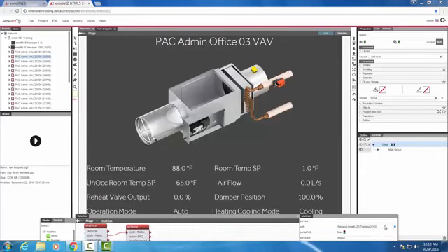In this how-to, I'm going to show you how to create a template graphic using the Relativize block. So this is what I'm going to show you how to do. If I've created this VAV template and I want to switch out the device reference so that my graphic is a template, I would just change the value of the Relativize block. Notice on the bottom here how I am changing the device reference from 20102 to 20103, etc. And you can see all of the values of the graphic changing.